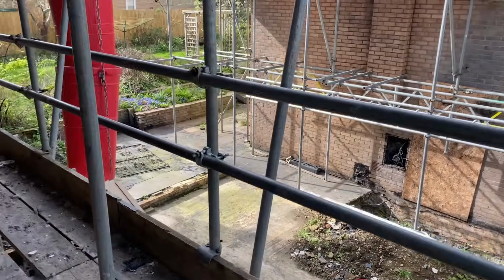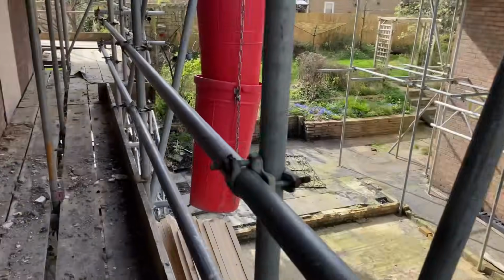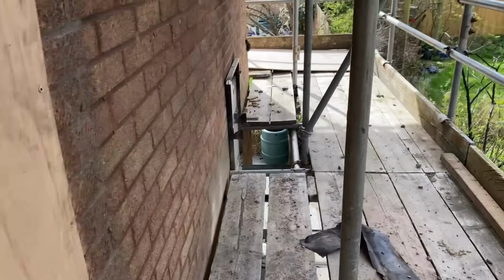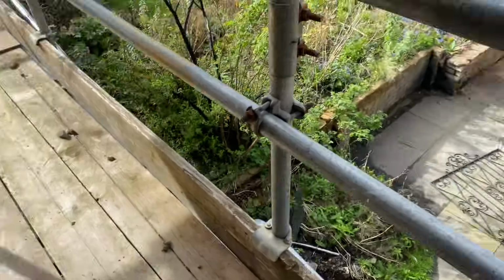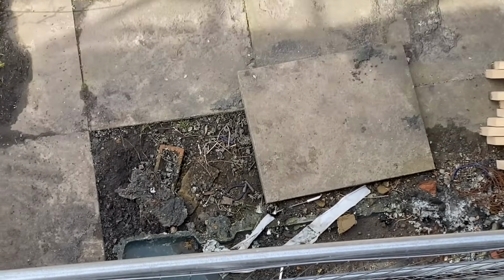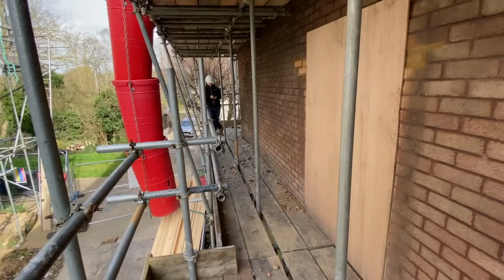When we did one of our original inspections here, there was the remains of a garage, and that's next door's house, also with a tin hat, because they've also suffered quite significant damage. So this particular job, I think we can say now, I don't think there's any issues with it, but the fire started on an outside boiler, which then, the pipe to the boiler melted, dripped down, and next door's garden, there, just in there, you've got the plastic oil tank, and that set fire to the garage, which then turned around and set fire to the house and set fire to next door's house. So it's a big chain of events that's caused quite catastrophic damage.